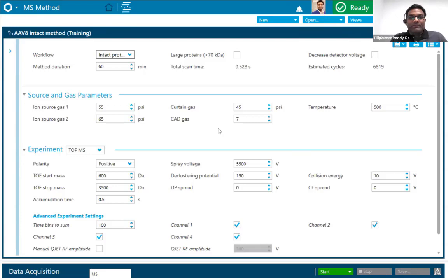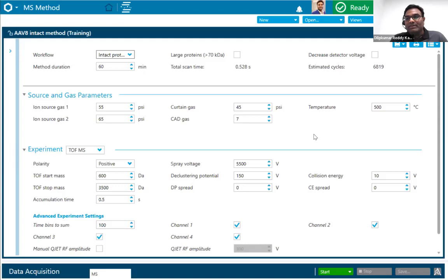The main purpose of these parameters is to completely and efficiently evaporate or dissolve the mobile phase entering the source of the mass spec. Once you optimize these source and gas parameters for a particular flow rate — say 0.25 mL per minute — you can use the same parameters for any other protein or sample analyzed at that same flow rate. We don't have to optimize for each and every different sample at the same flow rate. That is one of the advantages.